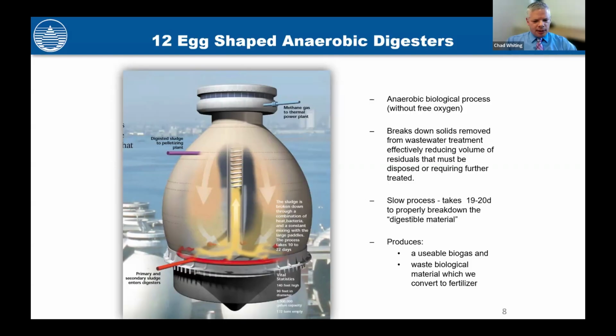The gas production is about 190,000 cubic feet an hour. We get about 17.5 cubic feet of digester gas per pound of volatile solids destroyed, and about 65% methane, with a BTU value of 622 BTUs per cubic foot. The egg shape is more efficient than our previous pancake-style digesters, which yielded 15 cubic feet per pound of volatile solids destroyed.